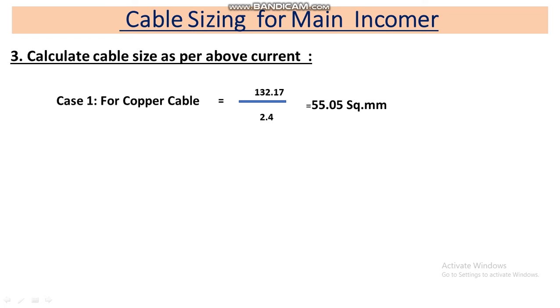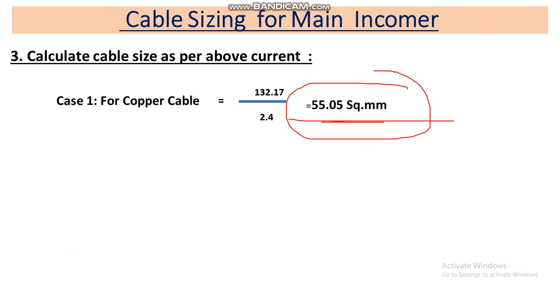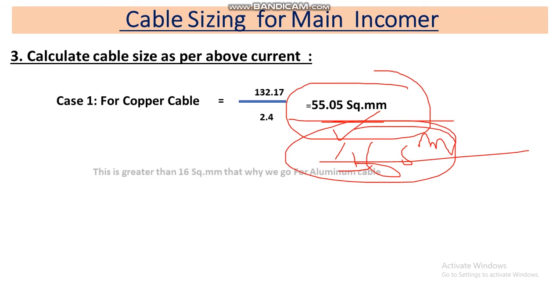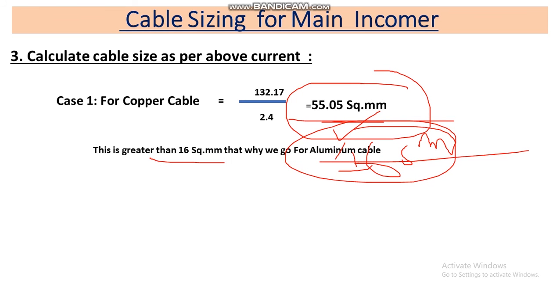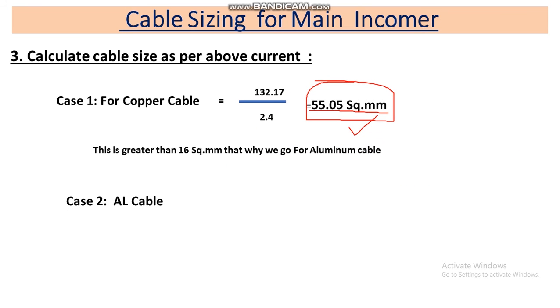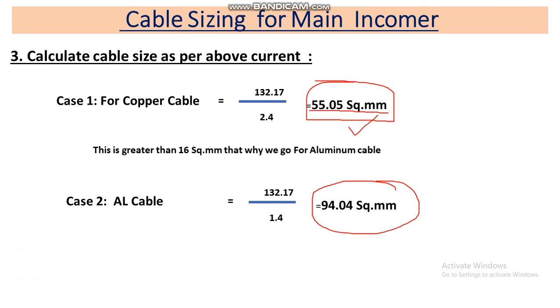Now in Step 3, first we check for copper cable. One square mm copper cable carries 2.4 A, so: 132.17 ÷ 2.4 = 55.05 square mm. Since this is more than 16 square mm, we go for aluminum cable. For aluminum, one square mm carries 1.4 A, so: 132.17 ÷ 1.4 = 94.04 square mm. This is the aluminum cable size.